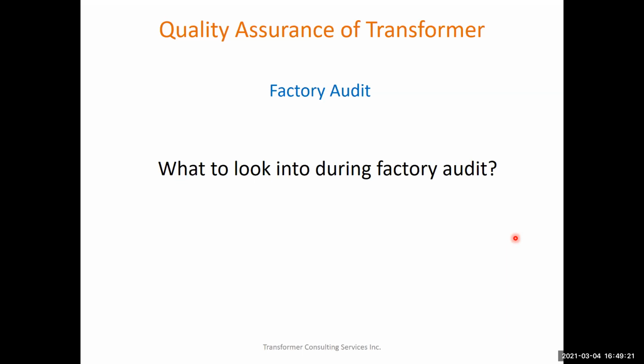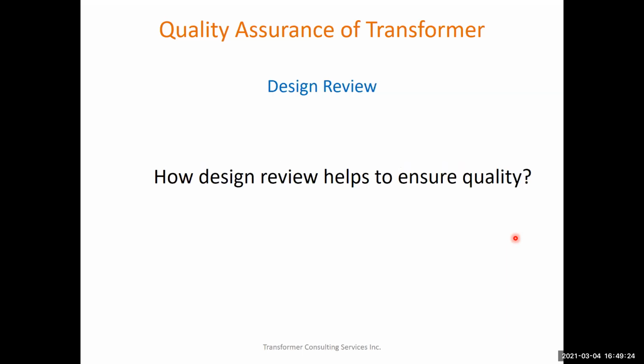So once we point those things out in the factory auditing report, the next thing we do when procuring the transformer is, after we issue the PO, we tell the manufacturer that once they finish the electrical and mechanical design, they have to provide us the design for review. And they cannot procure any material - not the conductor, not the core steel, not the insulation package - until we, the client, review and approve the design. Once we approve it, the manufacturer can go ahead and procure all those materials for the manufacturing process.